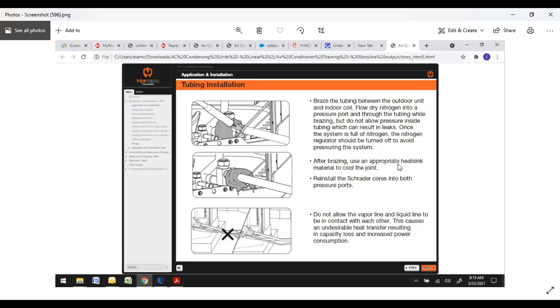After brazing, use the appropriate heat sink. Use that cool rag to wipe it down, cool the joint. Reinstall the Schrader cores in both pressure ports. And as you're running your lines, don't allow the vapor line and liquid line to be in direct contact with each other. This causes an undesirable heat transfer, resulting in capacity loss and increased power consumption.